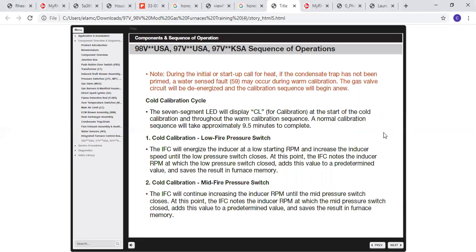During an initial startup or heat call, if the condensate trap has not been primed already, you will get a water sense fault 59 during the warm calibration. The gas valve circuit will be de-energized, and the calibration sequence will begin again. You'll know when you're in calibration sequence because the 7-segment display will display a CL, and that's for calibration. And there are two sequences of the calibration.